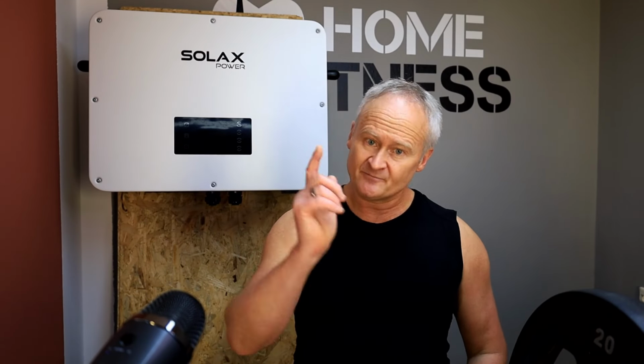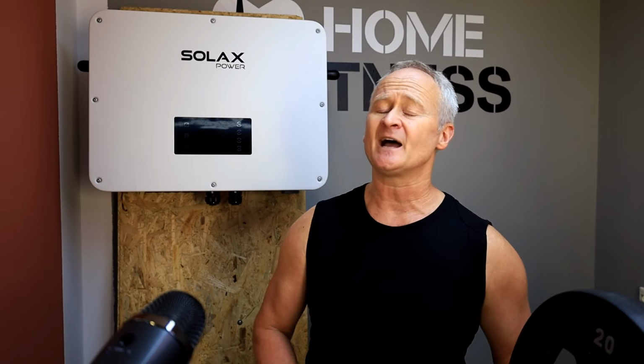Whether it truly makes sense to draw 35 to 50 amps of electrical current from the batteries is another important question. But with the Solax X3 Ultra, or rather, the excellent option to connect two separate battery strings, it's definitely possible, even with just one single battery string. Additionally, the new stackable battery system allows for significantly higher voltages. The voltage range goes up to 750 volts. This means that, if you want, you can use the new battery to take full advantage of the maximum possible voltage at the battery connection of any Solax X3 hybrid inverter.